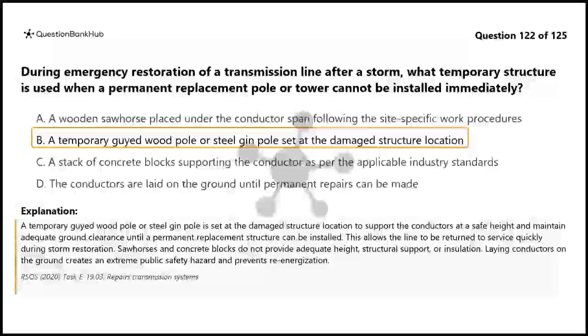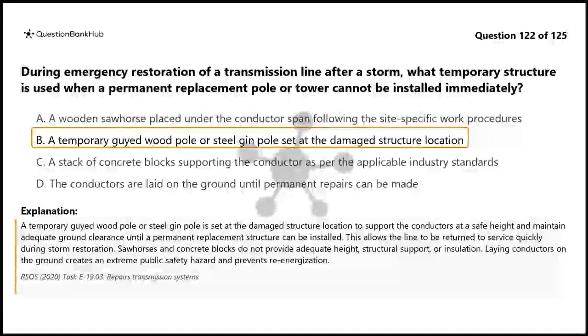A temporary guyed wood pole or steel gin pole is set at the damaged structure location to support the conductors at a safe height and maintain adequate ground clearance until a permanent replacement structure can be installed. This allows the line to be returned to service quickly during storm restoration. Sawhorses and concrete blocks do not provide adequate height, structural support, or insulation. Laying conductors on the ground creates an extreme public safety hazard and prevents re-energization.